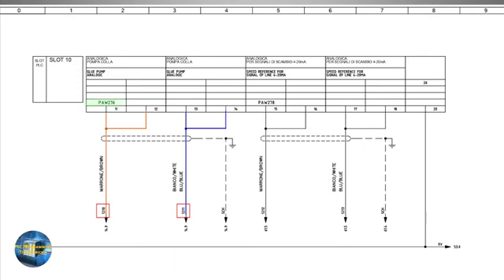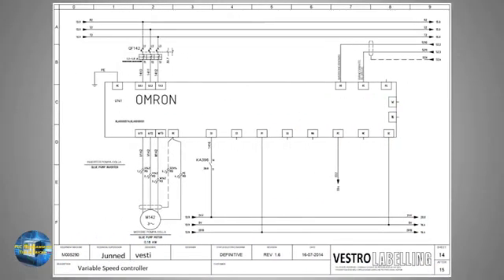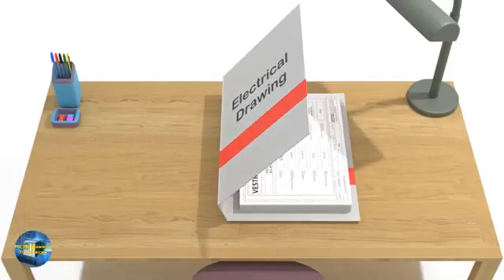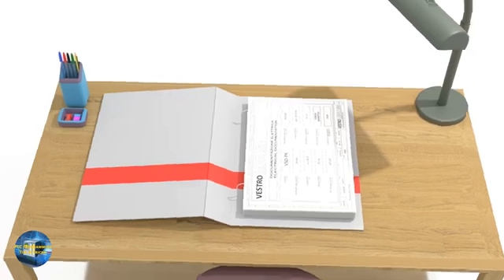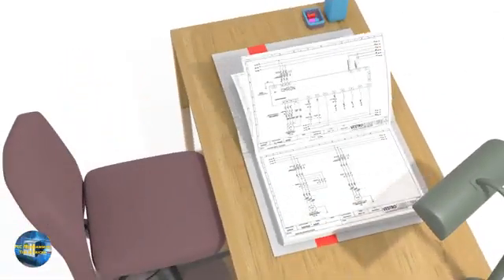If you look closely, PAW276 is mentioned above these terminals, which is the analog output address in the PLC program handling this particular analog output signal. So this is how to read the electrical wiring diagram. I hope now you have some basic information about how to read these diagrams.